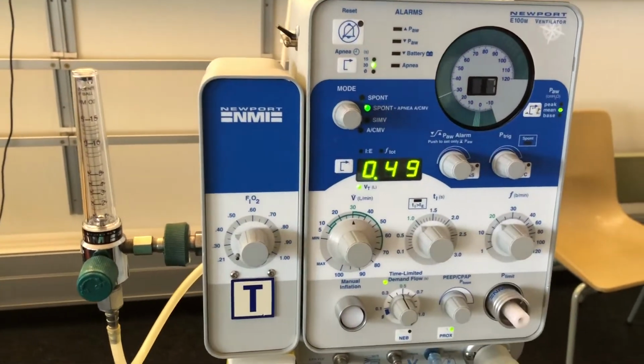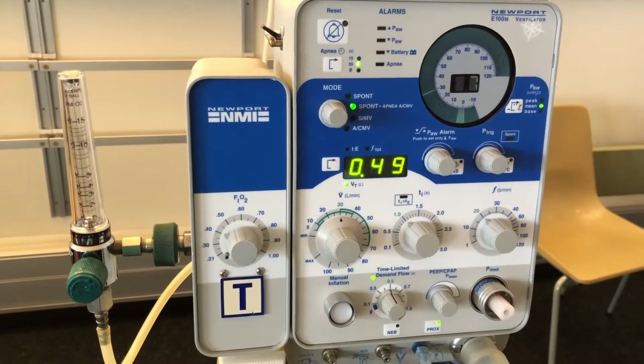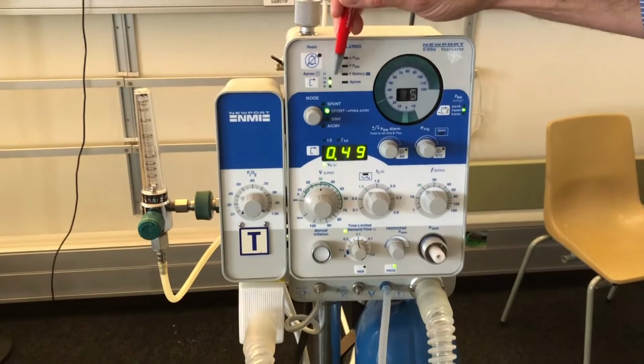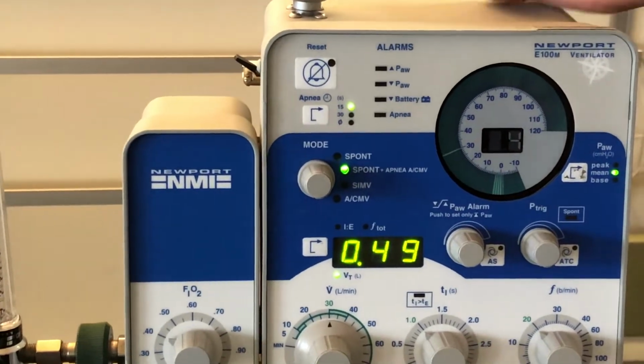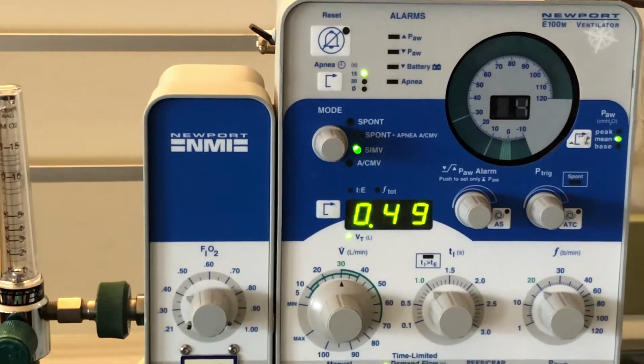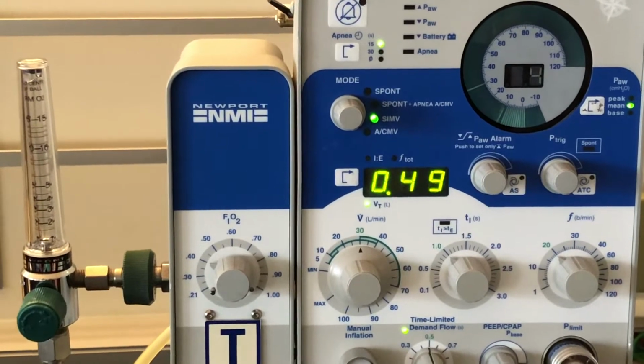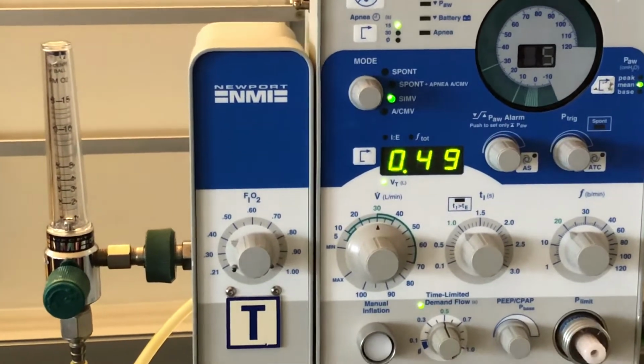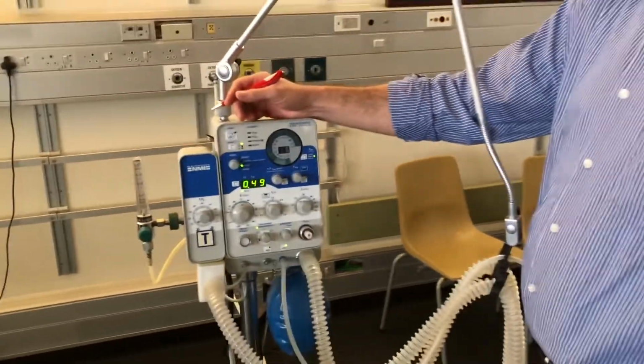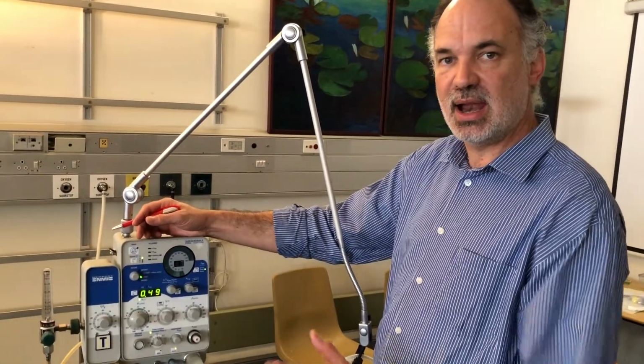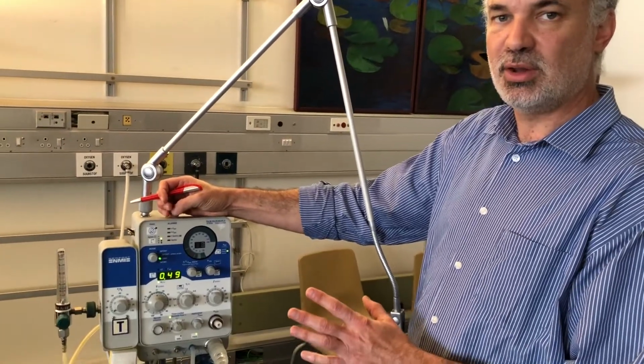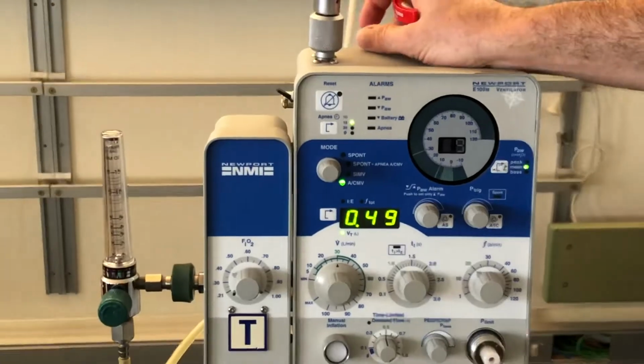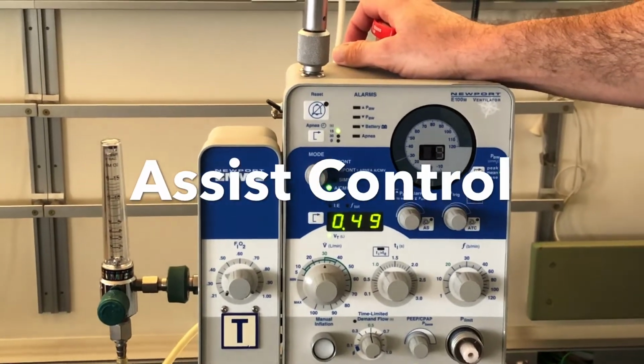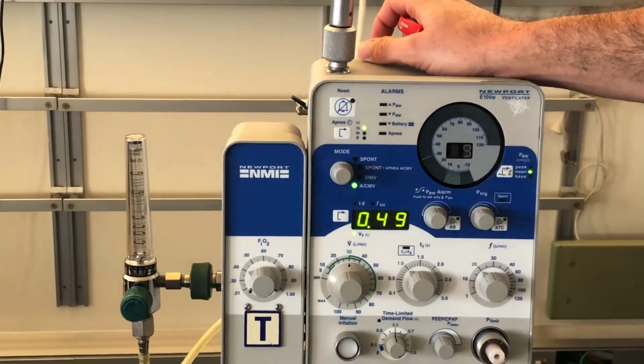nothing. The next setting is spontaneous respiration with an apnea backup. So if the machine detects an apnea in terms of a number of seconds that we can select, and the patient hasn't taken a breath within that period of time, the machine will initiate backup ventilation. Then there's SIMV, so that's synchronized intermittent mandatory ventilation, which we'll talk a little bit more about just now, but just to make you aware that this ventilator doesn't do SIMV with pressure support. So the machine does SIMV, and it does allow the patient to breathe spontaneously, but the spontaneous breaths are not pressure supported. And then the last mode that we have on the ventilator is assist control mandatory ventilation, which is the simplest mode of ventilation available on this ventilator.